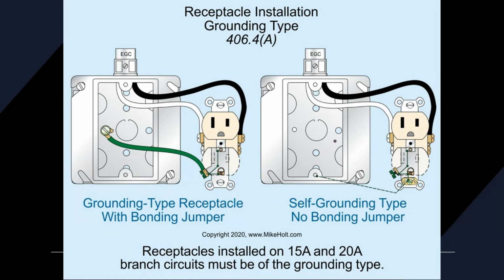406.4(A) is receptacle installation of grounding type receptacles. You can do this through a couple of different ways. You can run this bonding jumper, like you see here, to the box and over. But if it is a self-grounding type yoke, see this little copper yellow guy on the bottom here? If it is a self-grounding or listed as a self-grounding type yoke, you do not need this grounding jumper to go back to the box. The screw, if you use the factory screw or a 6-32 with at least 2 threads in the metal, it will count as bonding your screw, as bonding your receptacle.